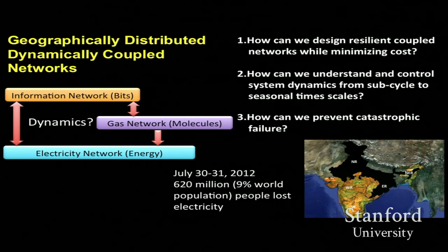And it turns out it happened because of something called cascading failure. It was hot summer, people were drawing a lot of current in agricultural pumps. Pumps consume reactive power as opposed to real power, they need reactive power, and the phase angle between the voltage and current shifted. In India, they didn't have controls on those, and you're drawing more current. Suddenly, one circuit breaker trips, and if one trips, all the load or power is shifted to the rest of the network, and then another one trips, and then you have a cascading failure.